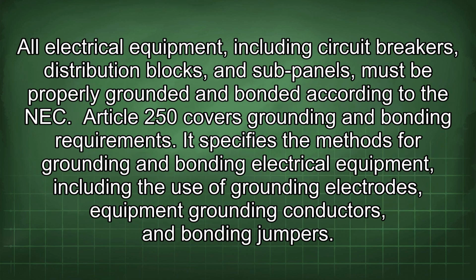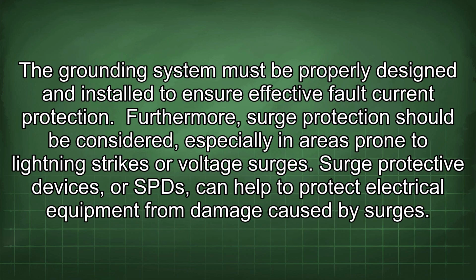All electrical equipment, including circuit breakers, distribution blocks, and subpanels, must be properly grounded and bonded according to the NEC. Article 250 covers grounding and bonding requirements. It specifies the methods for grounding and bonding electrical equipment, including the use of grounding electrodes, equipment grounding conductors, and bonding jumpers. The grounding system must be properly designed and installed to ensure effective fault current protection.